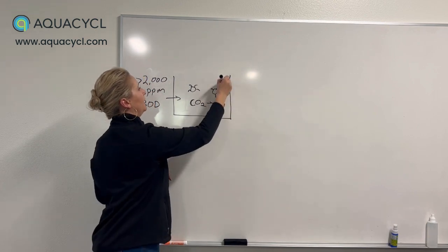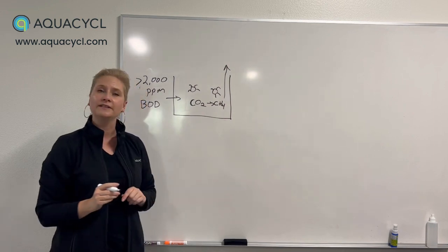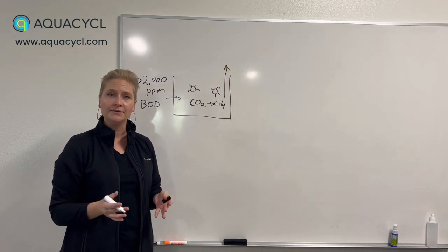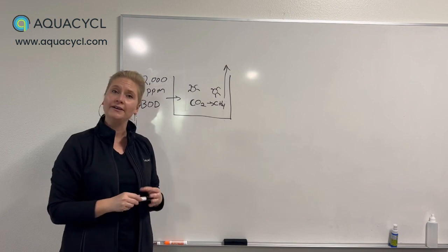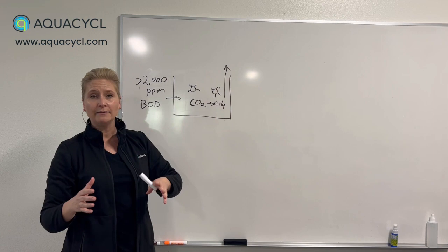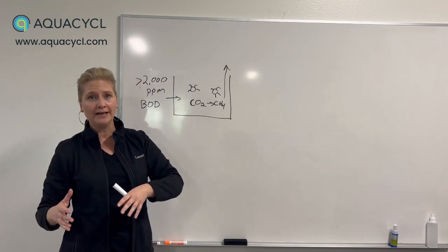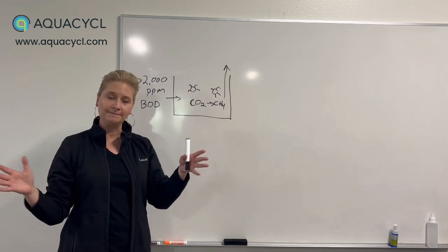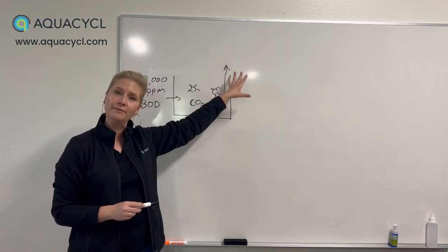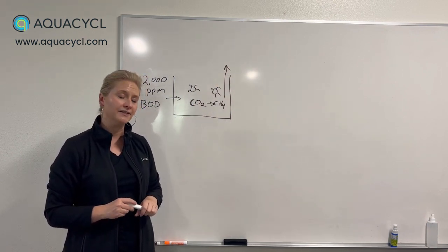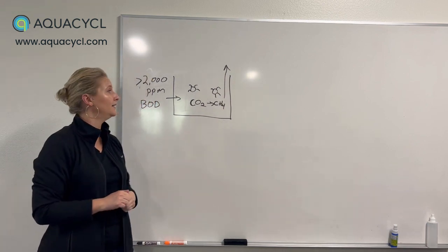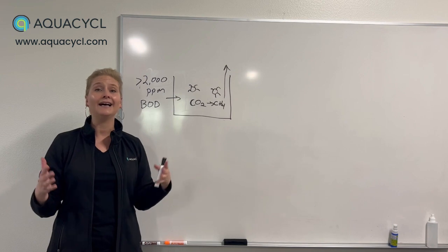And then that methane leaves the anaerobic digester, and you can capture that biogas and use it to produce energy through a method called cogeneration, where you purify the biogas and burn it to make heat and electricity. You can also supplement natural gas lines with the methane that you capture from an anaerobic digester. Now, the limitations with an anaerobic digester are space and time.